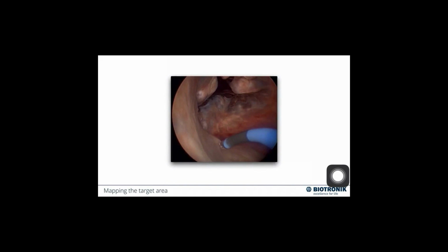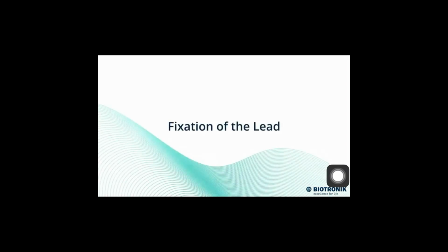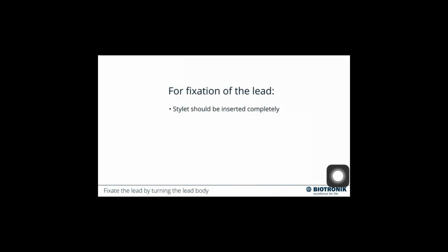Define the target area by mapping. Before fixating the lead, the stylet should be inserted completely into the lead and stable during lead advancement, positioning, and fixation. However, regardless if it is fully or partially inserted, make sure to avoid movements of the stylet, as this will change the distal curve of the lead together with the delivery catheter and might have an impact on placing the lead in the intended target area.